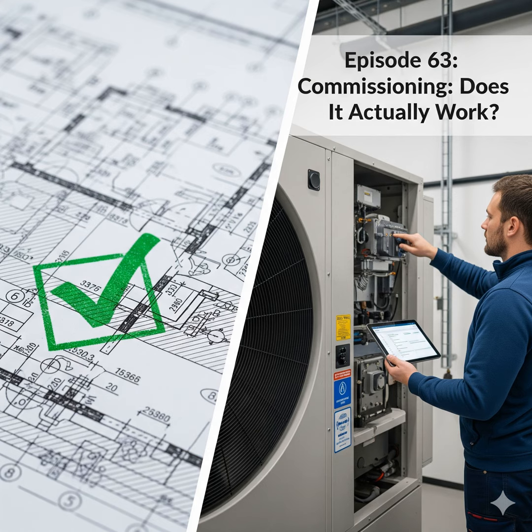Commissioning drives enhanced measurable energy performance directly. Think about the building envelope. The Builder's Guide to Hot, Dry, and Mixed Dry Climates details factors like air leakage, mentioning things like sealing gypsum board to the slab and frame using an airtight drywall approach. Those little details matter for airtightness. They matter hugely. Commissioning actively verifies these details during construction and through testing, like blower door tests. Ensuring the building envelope is as airtight as designed is absolutely critical for minimizing unwanted heat gain or loss. Less leakage means your HVAC systems don't have to work nearly as hard, saving significant energy. Like plugging the leaks in the bucket.